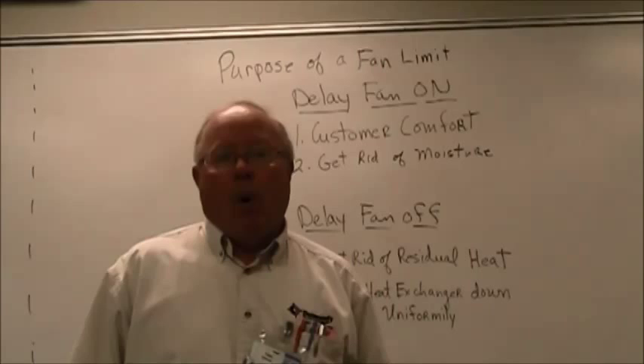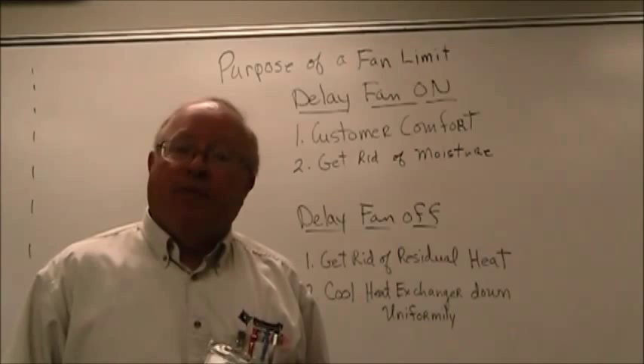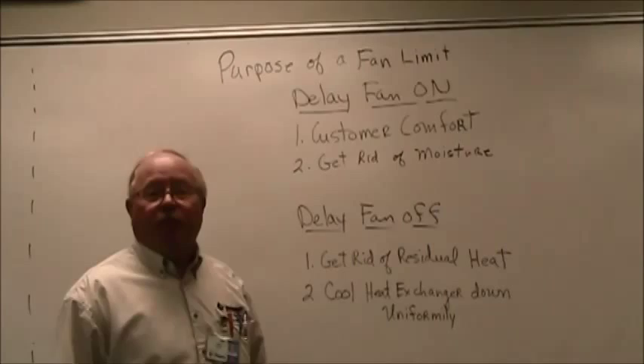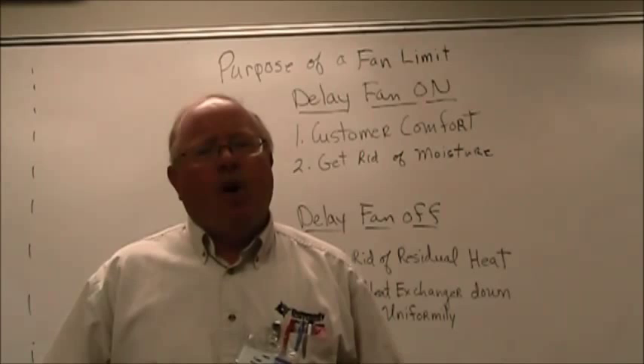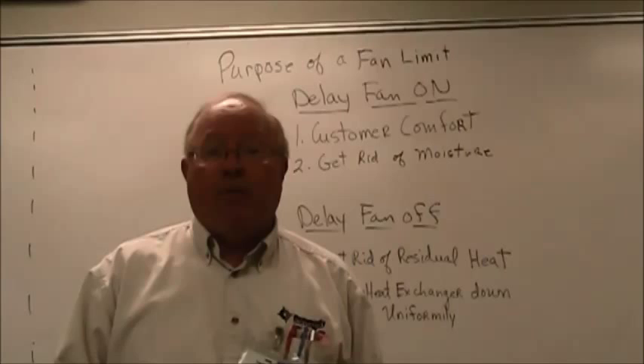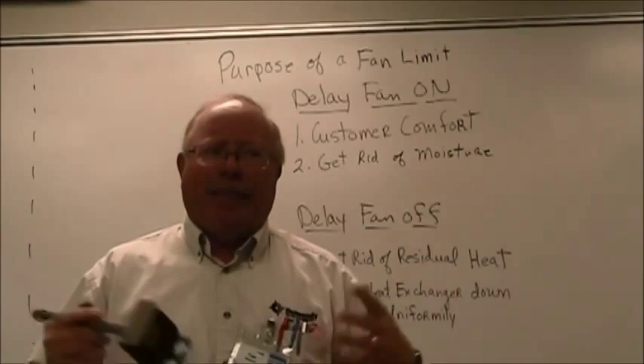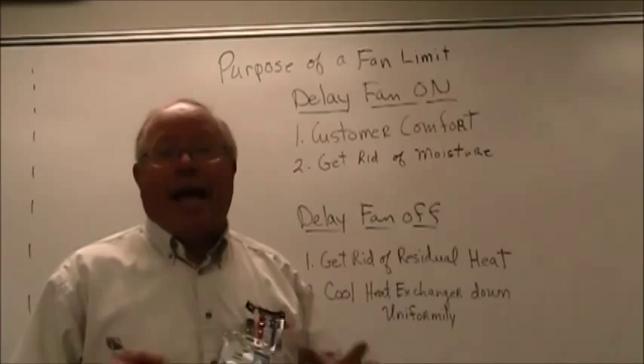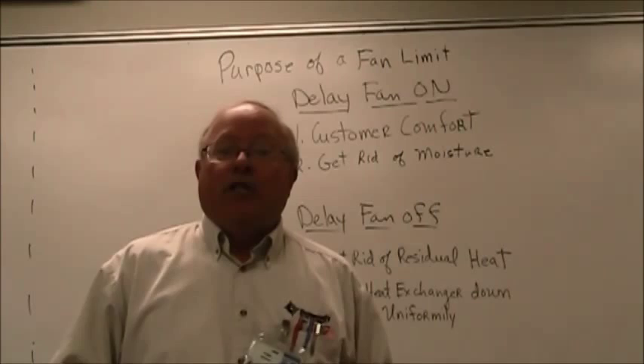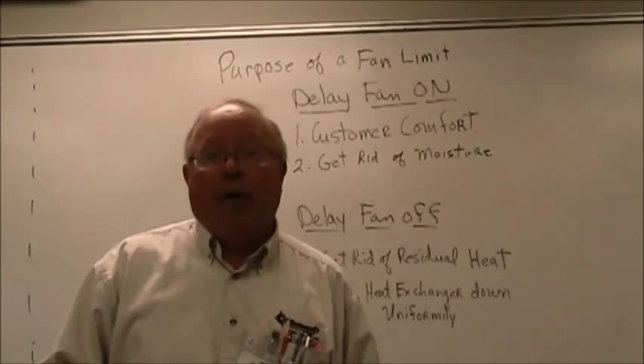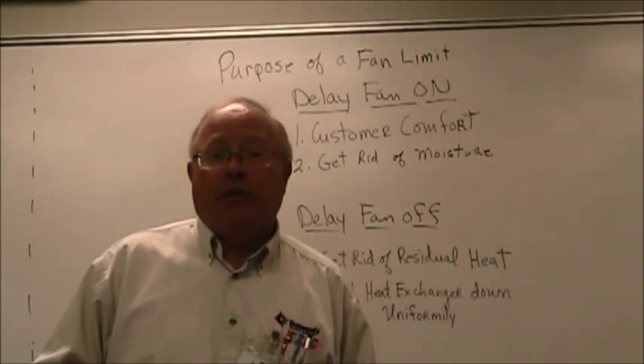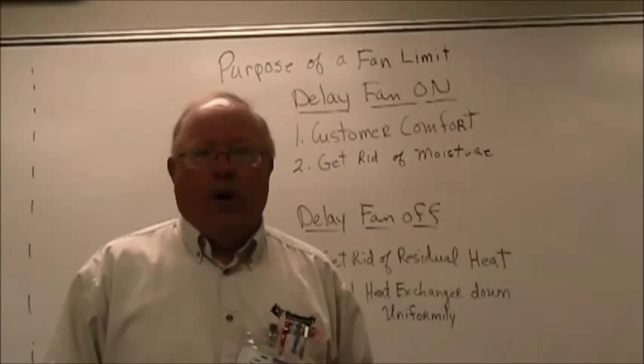But why do I want to delay the fan on? Why do I want to delay the fan off? Well, very simple reasons. First of all, customer comfort. When we bring the fan on, we don't want to blow cold air over somebody. We've all been in a restaurant or in a home where the fan, when it came on for the furnace, blew some cold air and it was a while before you started to feel heat coming out of the ductwork. So we want to turn it on at a time when we have infiltrated the ductwork with some warm air. We let the burner come on, we let it warm the air in and around the heat exchanger. That warm air rises and permeates the ductwork, so that when the fan does come on, it blows warm air over the occupants in the room.